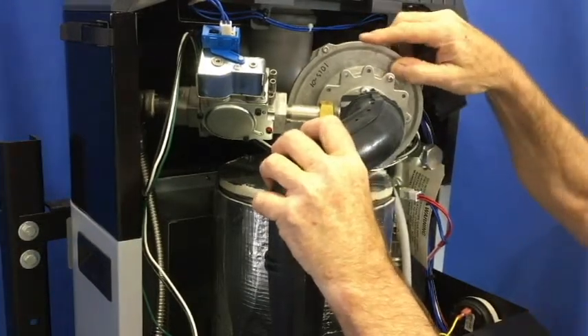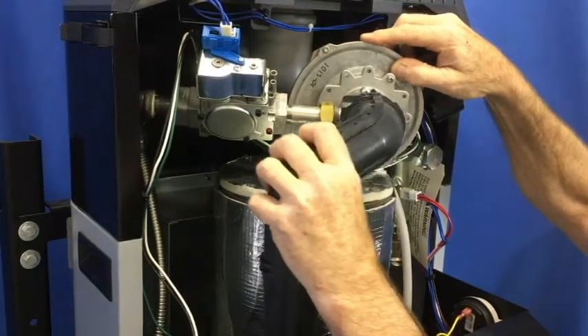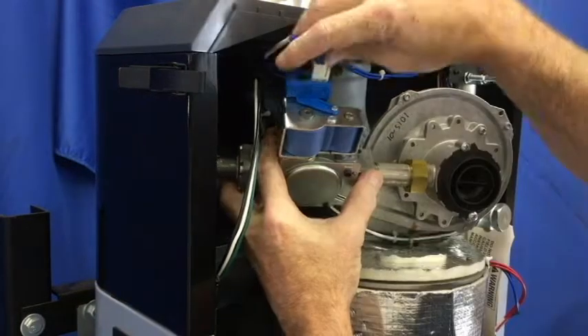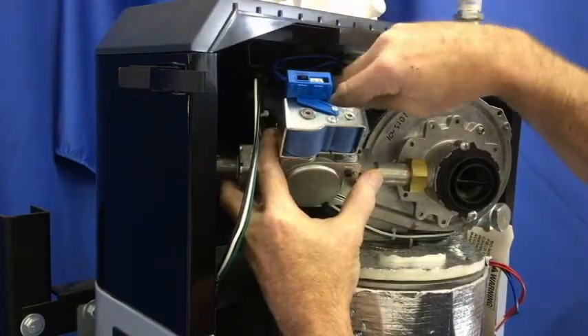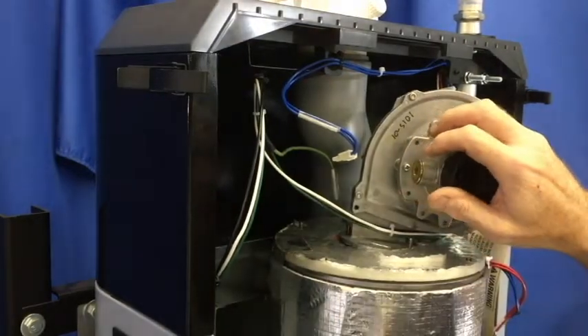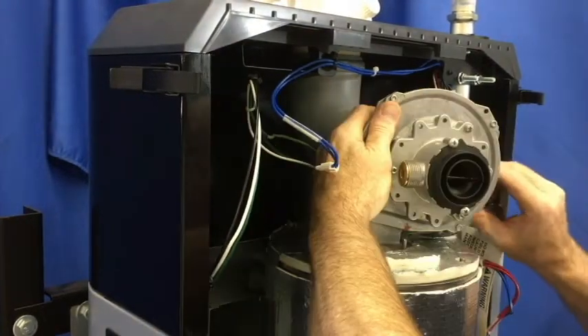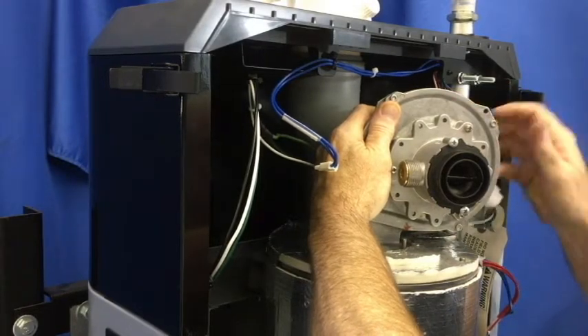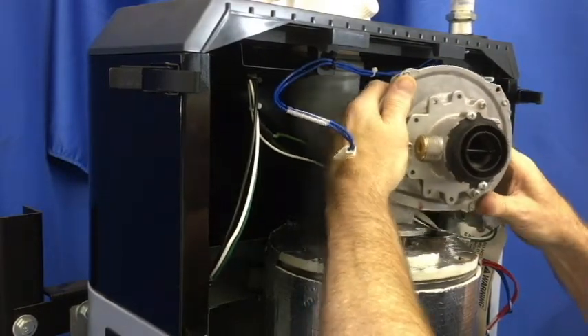Remove the air silencer, gas valve and flexible gas line. Disconnect the wire harness to the gas valve and blower. Disconnect the gas valve from the Venturi. Remove the blower Venturi assembly.